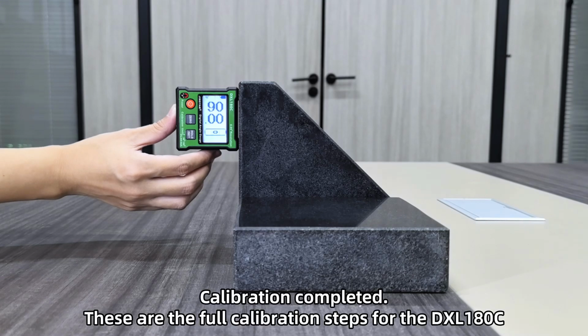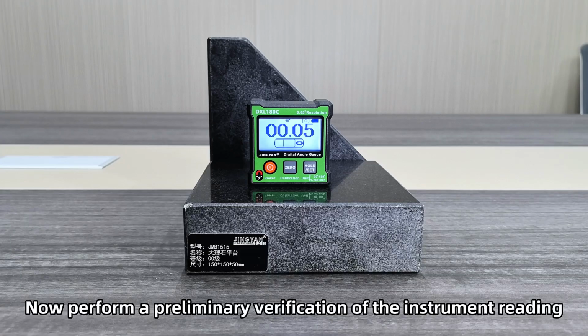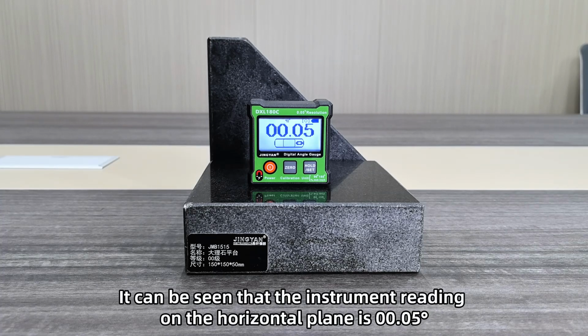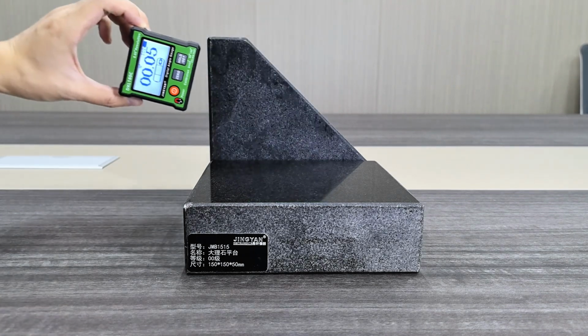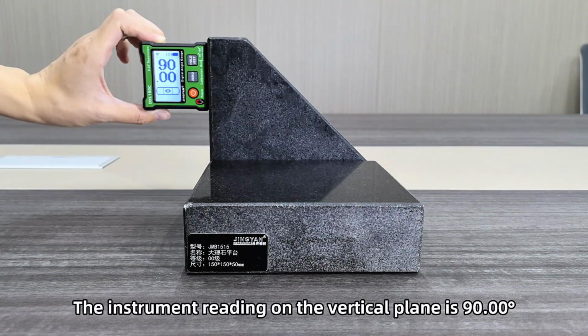Calibration completed. These are the full calibration steps for the DXL180C. Now perform a preliminary verification of the instrument reading. It can be seen that the instrument reading on the horizontal plane is 0.05 degrees. The instrument reading on the vertical plane is 90 degrees.